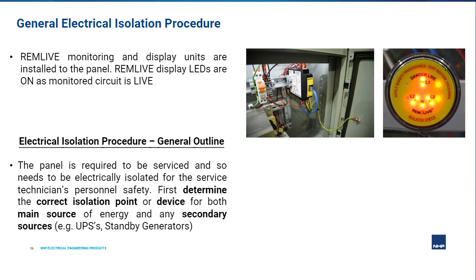They first need to identify the correct isolation point or device for the main source of energy, and isolation points for any secondary sources, for example, any UPSs, standby generators, etc. They also need to be considered as part of this process, which is quite important.